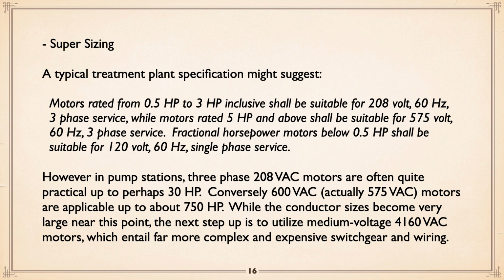The next step above that, the next choice beyond that voltage, is to go medium voltage, which classically today is 4160 volt. The problem with that is it's far more complex to deal with, and the switchgear and wiring are damned expensive. So I think that at 600 volts, 750 horse is a reasonable point. We ended up, I think, using 600 horse motors and went with 600.